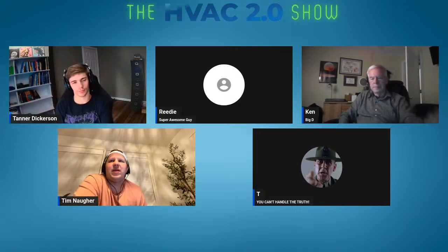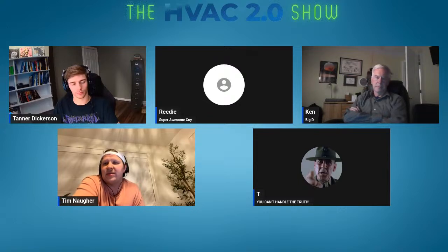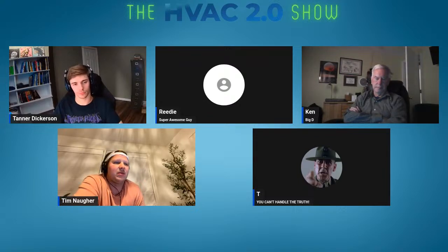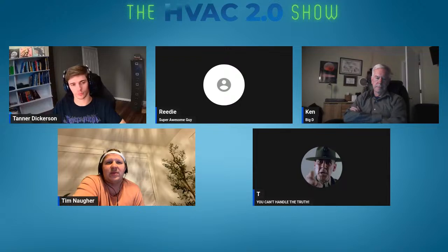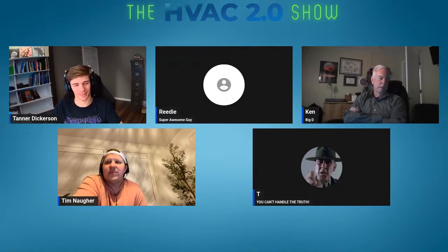I think they're going to need some kind of dehumidification for their top floor system. I mean, the load calc I've done is they need 2 tons of AC with 60,000 BTUs of heat, maybe even less than that, and they have 5 tons of AC with 120,000 BTUs of heat. So, the equipment's a year old, so probably change the equipment.